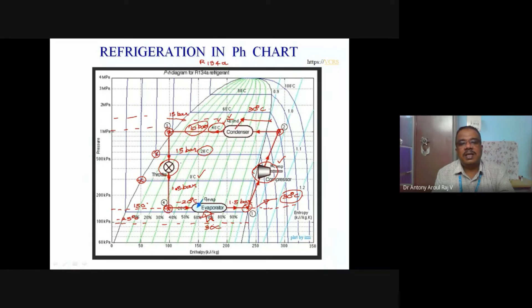Okay, similarly, by knowing this, you may be thinking that the compressor is the important component of the refrigeration system, but that is not so. I would say that your expansion valve is equally important, because at the upstream of the expansion valve there will be high pressure, 10 bar, 15 bar. At the downstream of the expansion valve you will have a low pressure of around 1.5 bar. This pressure difference, 15 bar and 1.5 bar, is maintained by the expansion valve only.